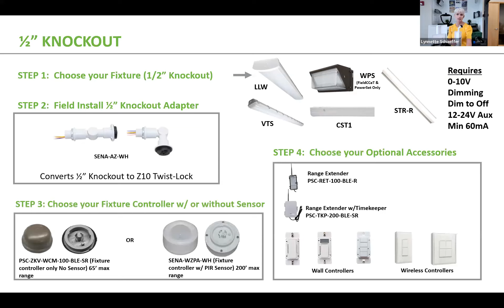I want you to be aware this isn't something you can wire into any fixture. For this adapter and sensor to work, the fixture needs 0 to 10 volt dimming, a dim-to-off driver, 12 to 24 volt aux power, and a minimum of 60 milliamps. A lot of fixtures already out there don't have all of that, which is why only a handful of fixtures, as shown on screen, allow you to use this adapter to convert a fixture to a Z10 receptacle, letting you add standalone or network lighting controls. That's the main point I wanted to cover with that slide.